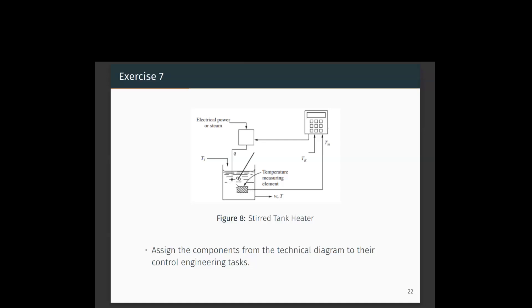The variable that we are trying to control is the temperature of the tank. The temperature measuring element — the sensor — feeds back to the controller. The controller has a reference input along with the present measurement, and it compares both. For example, if you want to maintain the temperature at 25°C, the reference is 25°C, and the current measured temperature is 20°C, then Tm is 20 and Tr is 25 — the difference is 5°C.